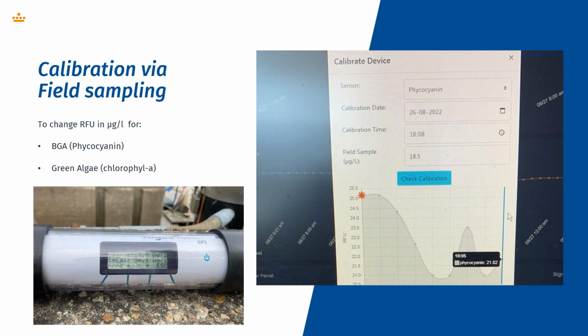Here is an example of how to calibrate via a field sample. You can change the relative fluorescence units into microgram per liter for the blue-green algae, so the phycocyanin, and the green algae measured by chlorophyll A. On the right side, I've made a picture of a pull-down menu. When you click on the button to calibrate the device, this is shown. You can enter the sensor which you want to calibrate, in this case, the phycocyanin.